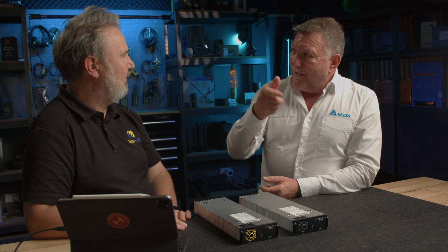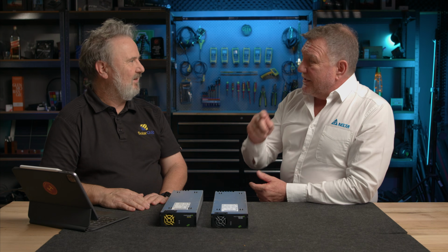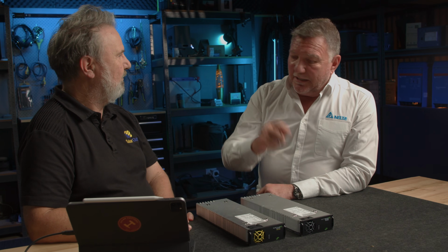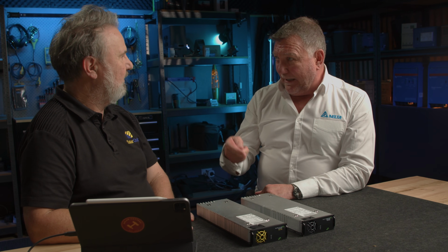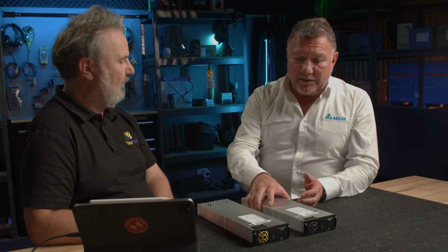Very easily - just buy the module, put it in the slot, and hit the reset button, because there's an asset register within the controller. By populating each slot and hitting reset, it updates the asset register, seeing the serial number of the system and entering that into the controller memory, along with the date it was installed. So you've got a good record of when the warranty started and the serial number of the module.